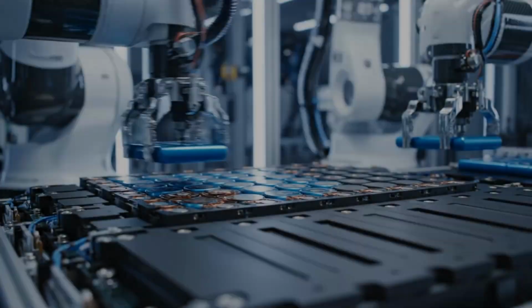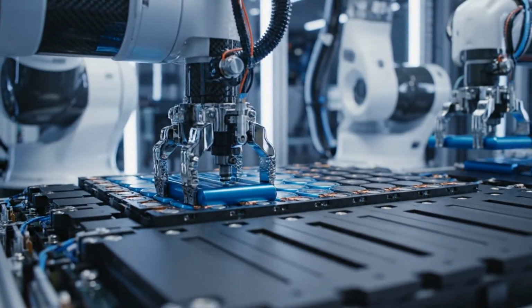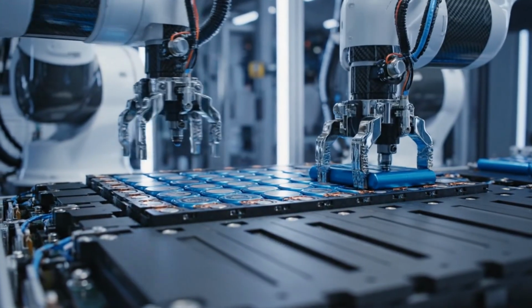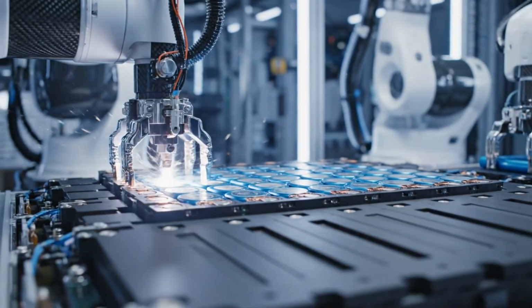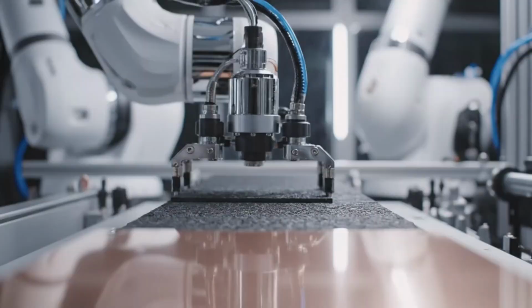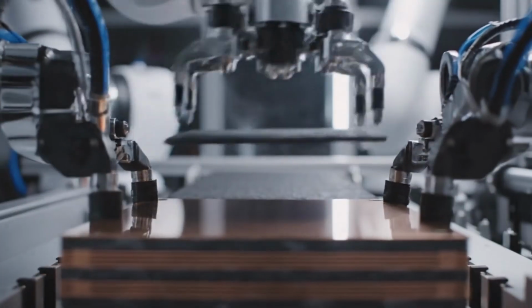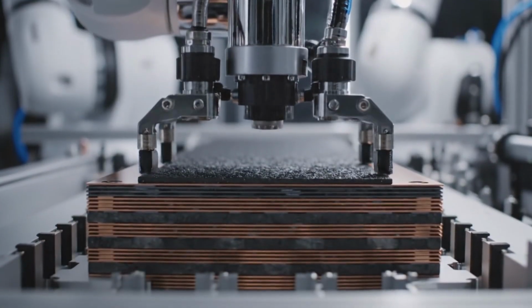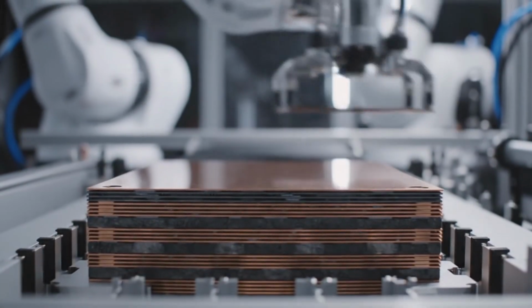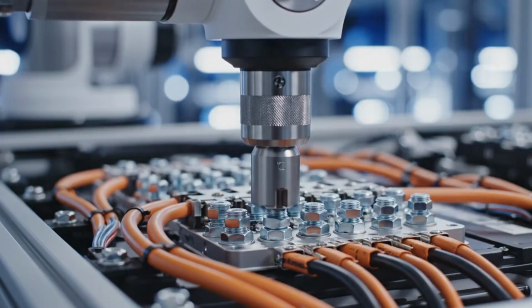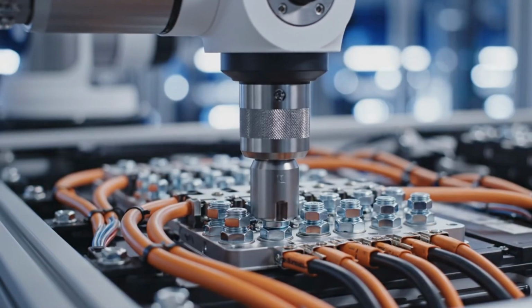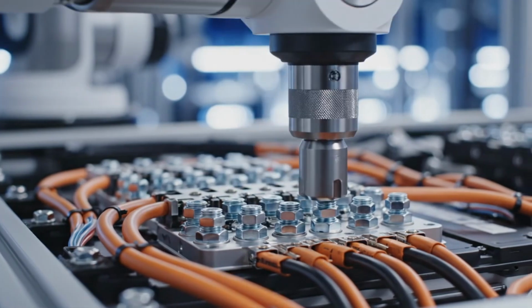Battery management systems are validated in parallel. BMS hardware and software are tested for accuracy, redundancy, and fault detection. Voltage sensing, temperature monitoring, balancing algorithms, and safety cutoffs are verified under simulated failures. The BMS is treated as a safety-critical system, not a convenience feature.